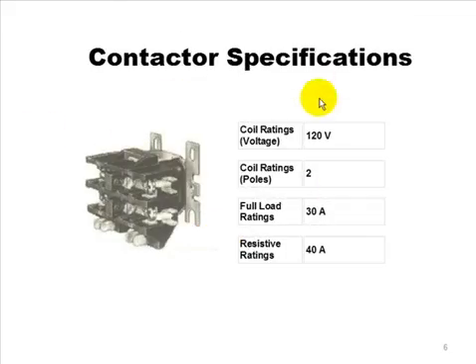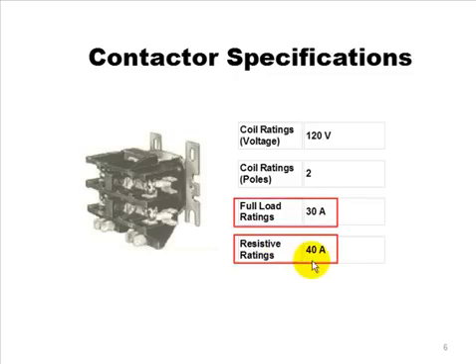You'll also see contactors specified that way. You'll have a, this coil, in this case, and this contactors, is 120 volts. There's two poles, you know, two poles. Full load amps is 30 amps. And the resistive load is 40 amps. You can take a higher resistive load because there's no inductance. You're not going to get that surge of voltage and current like you get in inductive loads.